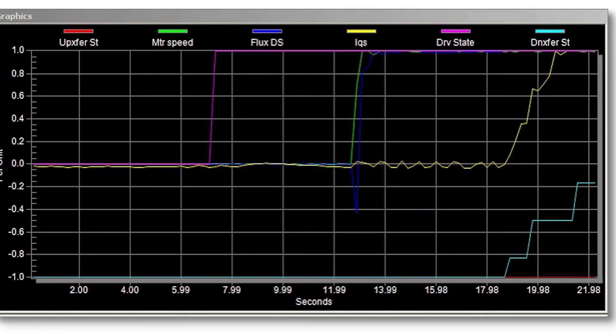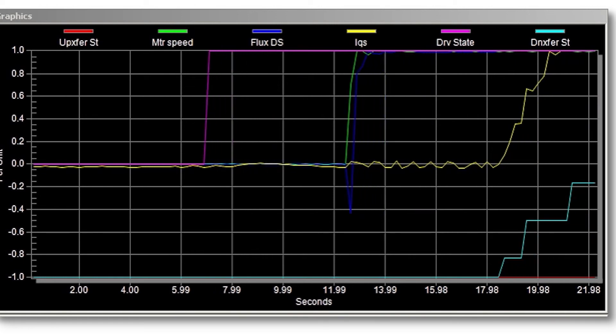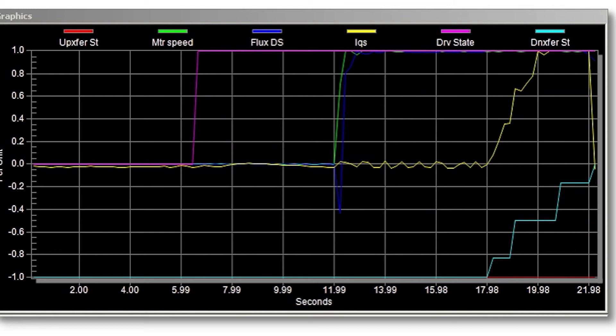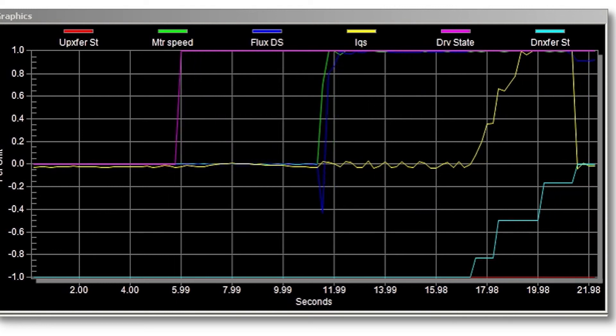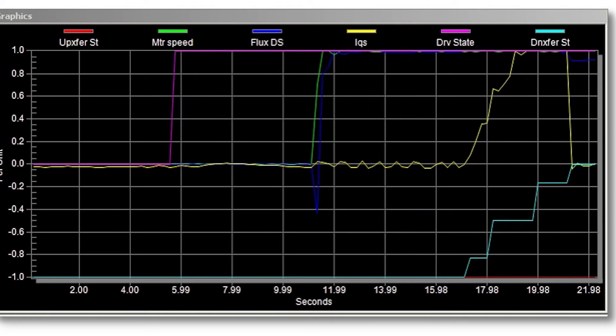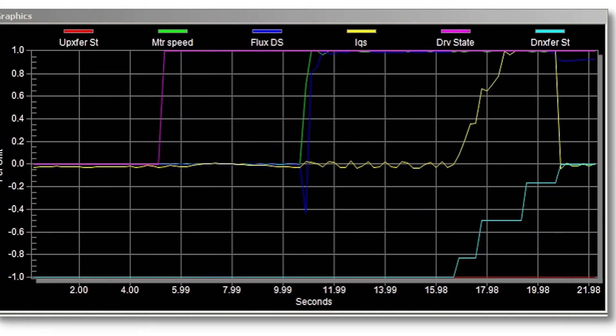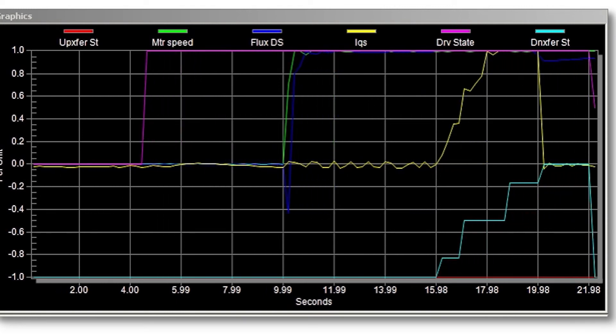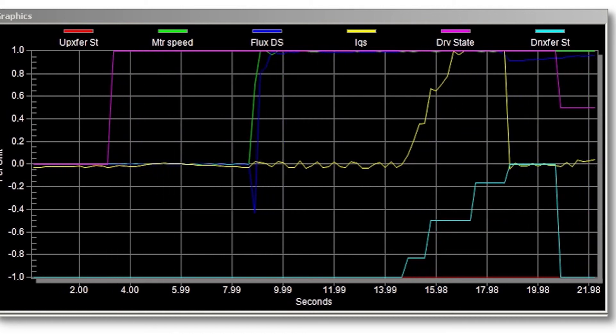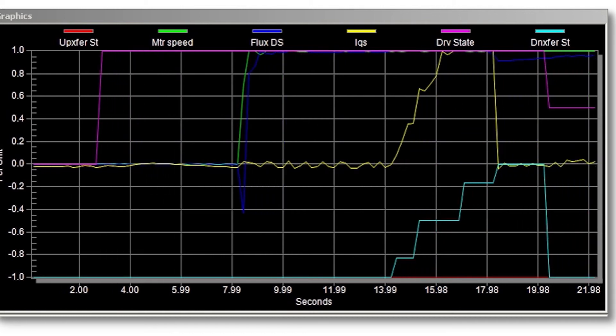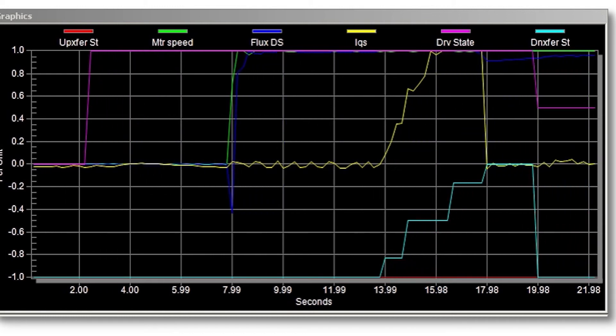Now the VFD is supplying power to the load and the line can be disconnected from the motor. The VFD then issues a signal that the bypass contactor L1 can be opened and the VFD has control of the motor.